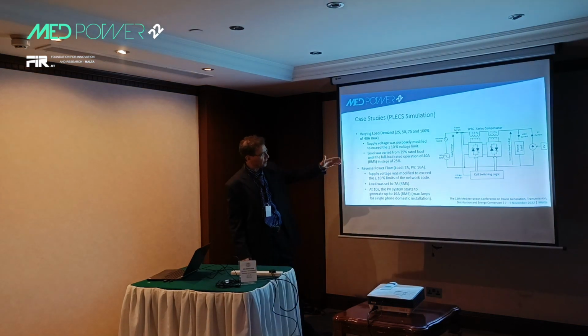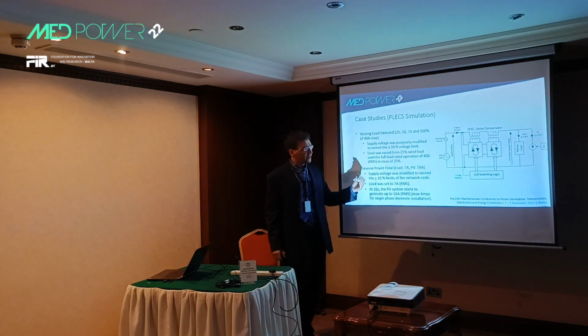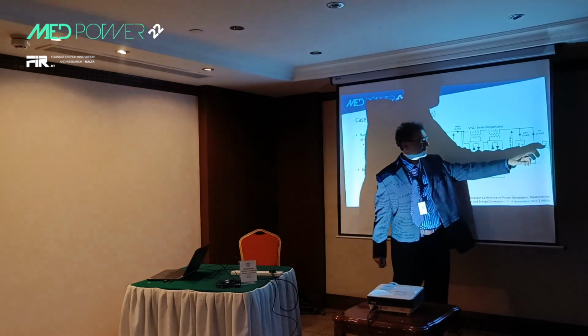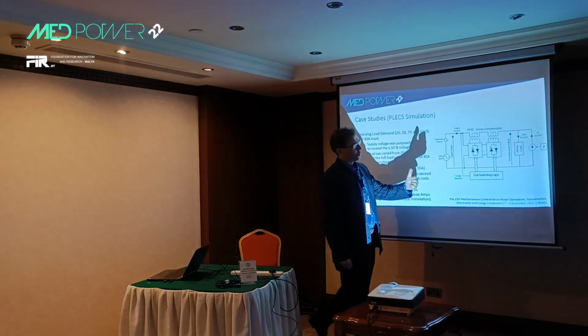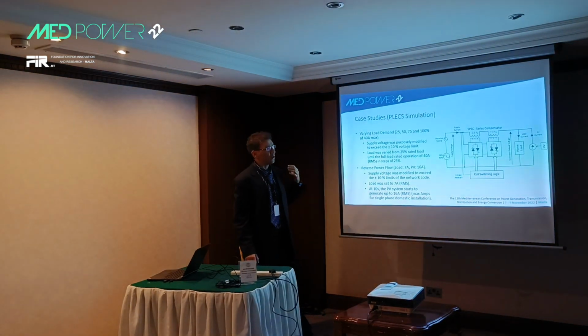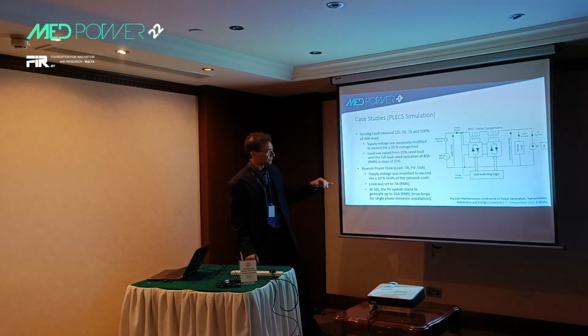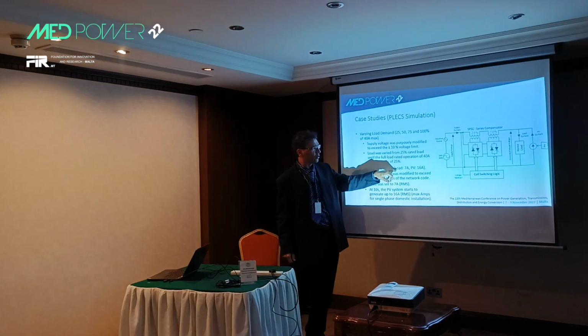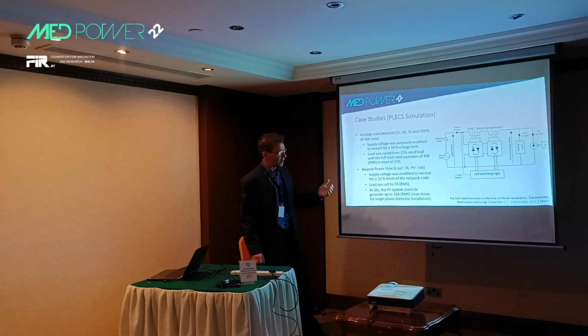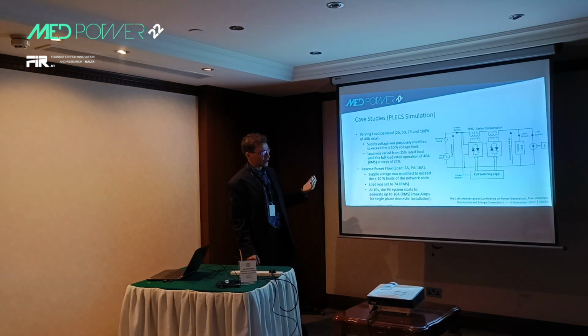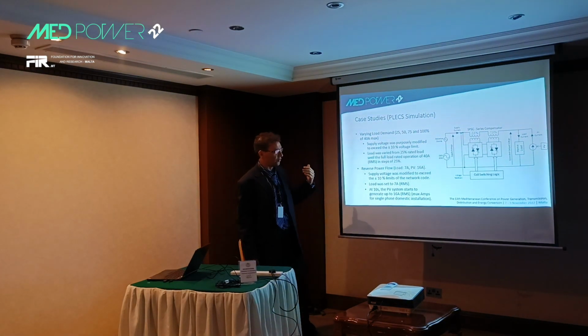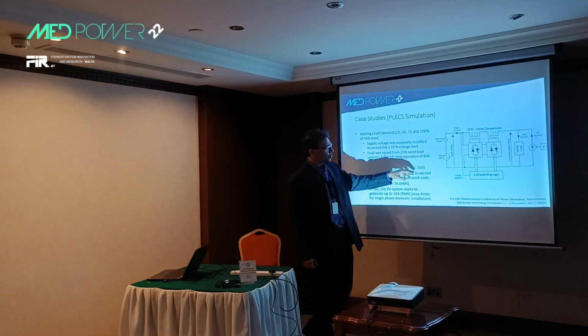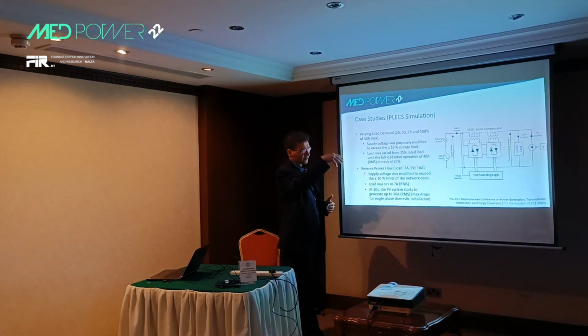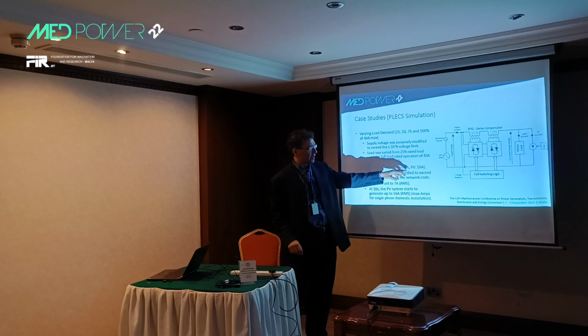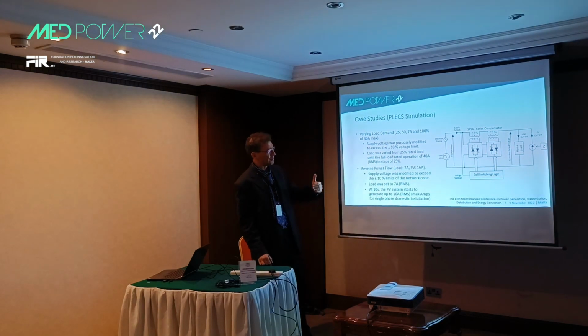So the simulation ran that load. On the other hand, we also tested the circuit whilst having a reverse flow of photovoltaic energy. So in that case, we lowered down the load to around 7 amps, because that is the case when you're going to have PV power flowing back into the grid. And we ramped up the PV, now you see it on the next slide, we ramped up the PV current from 0 up to 16 amps.